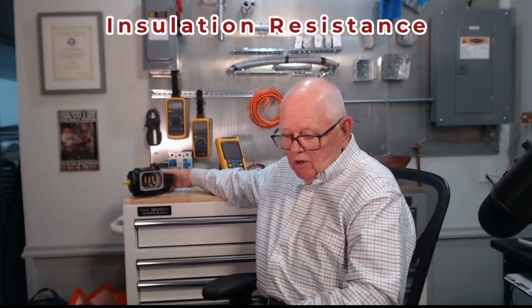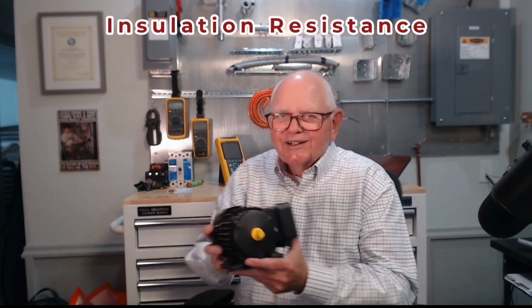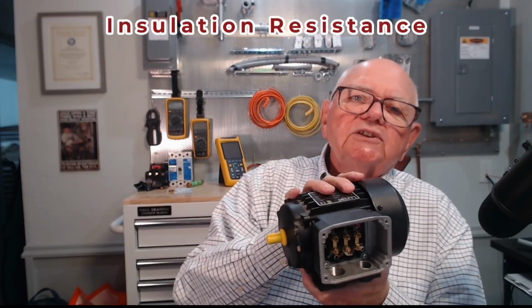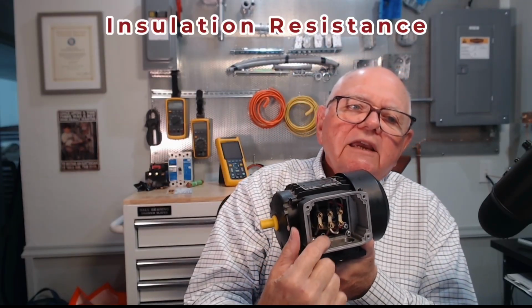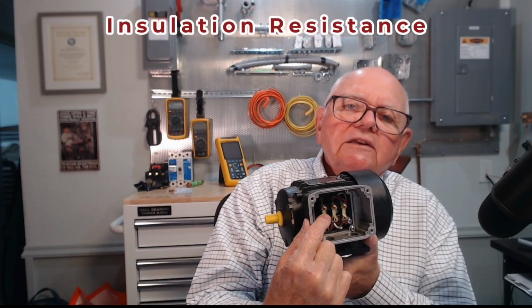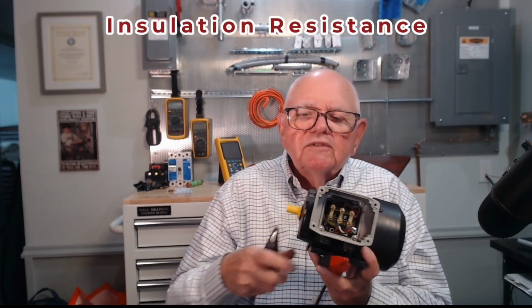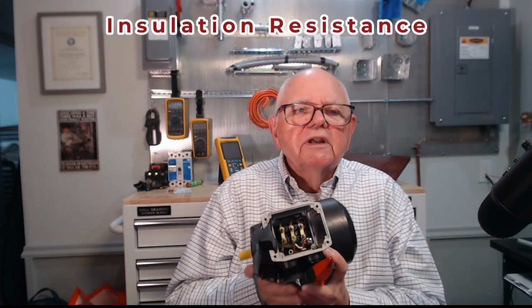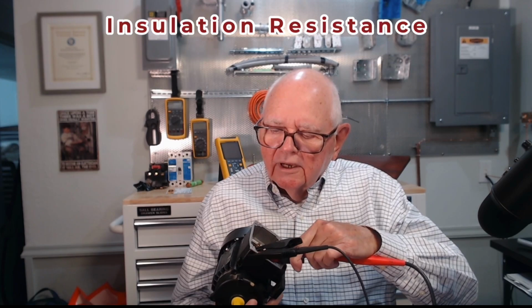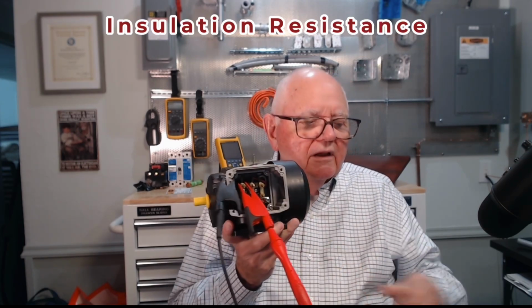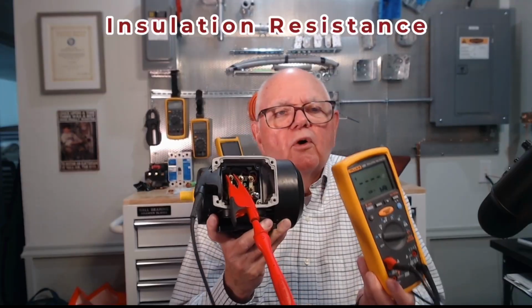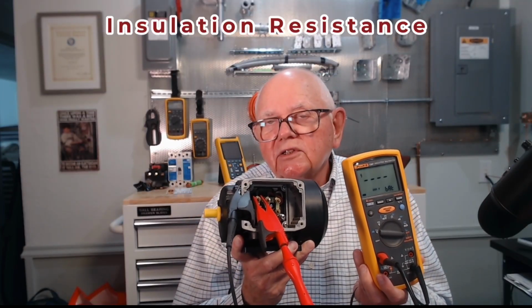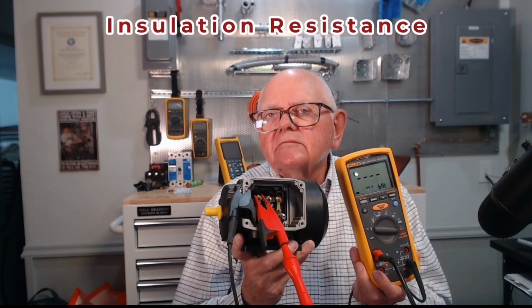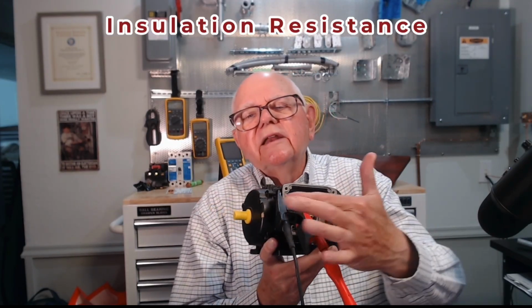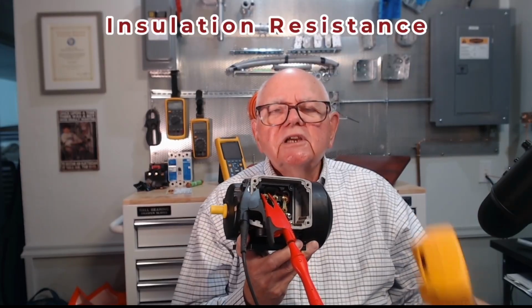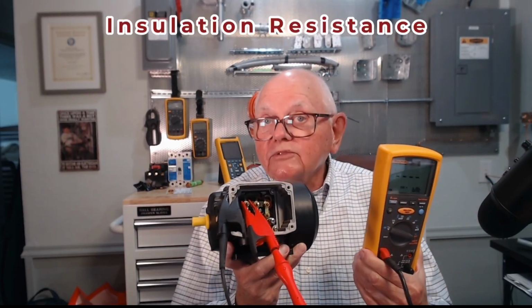Let's take a three-phase motor, for example. On a small three-phase motor, I've got insulation on the windings on the inside. I'm going to take into these terminals, they attach to the windings. So I can take something like my insulation resistance tester, find a good ground, connect one lead to ground, connect the other lead to either A phase, B phase, one at a time. And then I can apply voltage from my insulation resistance tester to those windings, and the current will flow into the winding. If any current leaks through the insulation and into my ground lead, my insulation resistance tester is calibrated to read out in ohms of resistance.